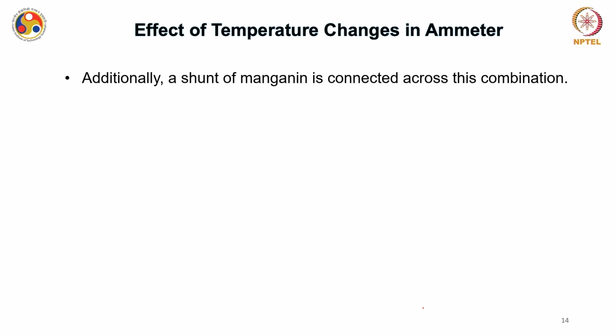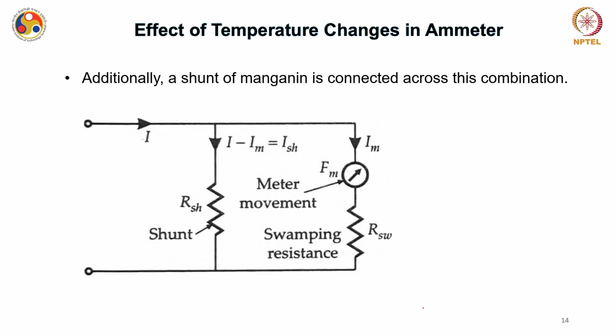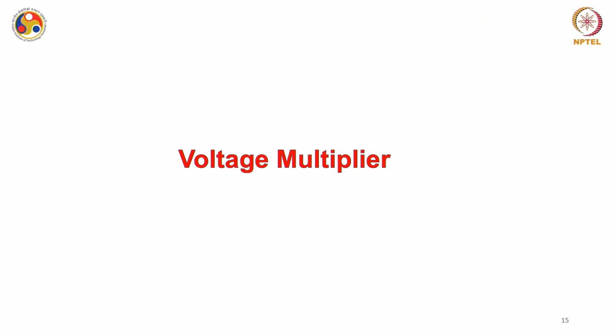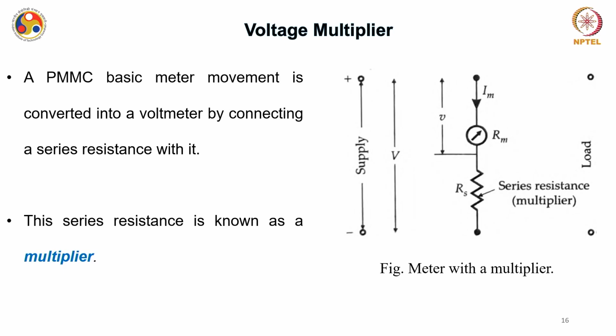So a swamping resistance is sometimes required. Additionally, a shunt of manganin is connected across this combination. So you have a meter resistance, you have a swamping resistance, and across it the shunt is connected, something like this. You have this swamping resistance, this is the meter resistance, and this is the shunt. You have this arrangement just to overcome the issues arising from temperature. Temperature plays a very crucial role in ammeters, and that is how you try to tackle it. Now, let us see how voltmeters are made using these DC meters.